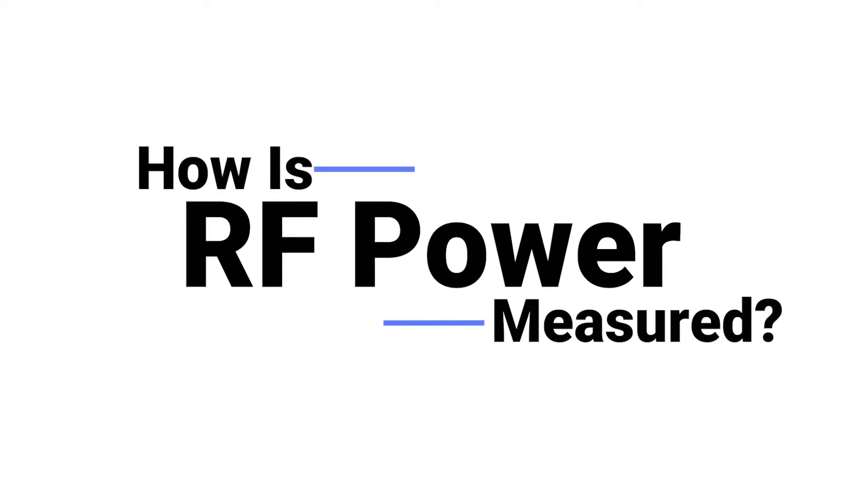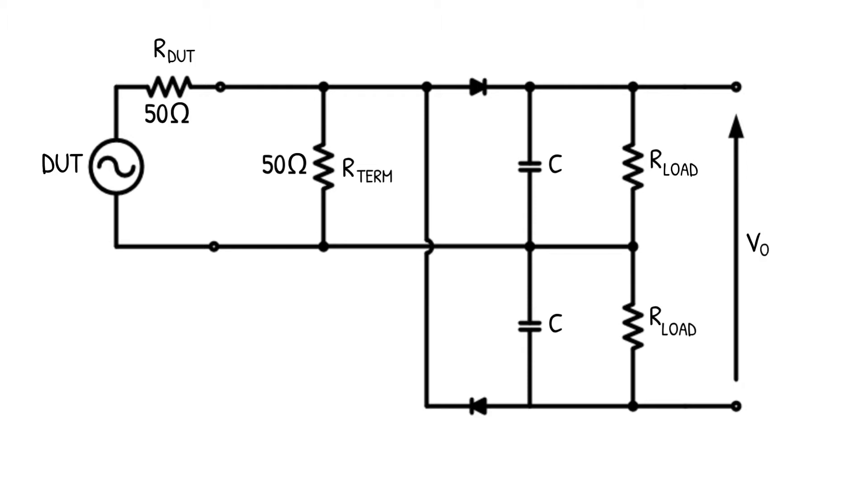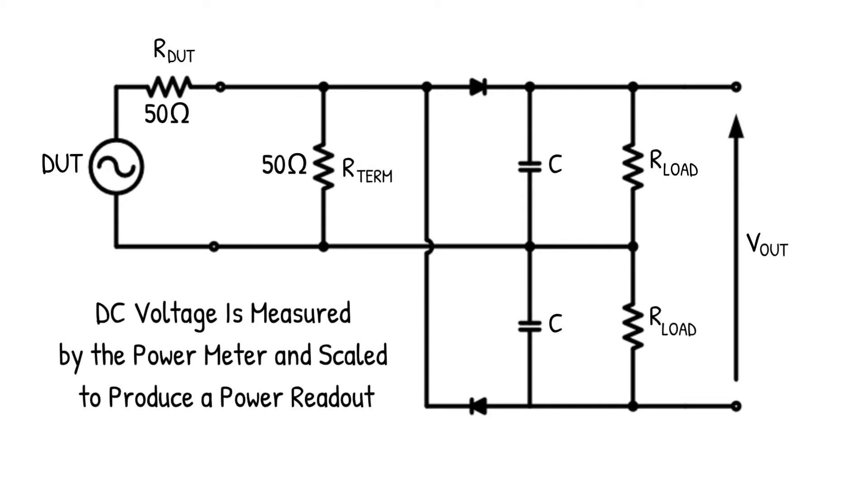How is RF power measured? To start, high frequency diodes detect the RF voltage developed across a terminating load resistor. The diodes directly perform an AC to DC conversion, and the DC voltage is measured by the power meter and scaled to produce a power readout.